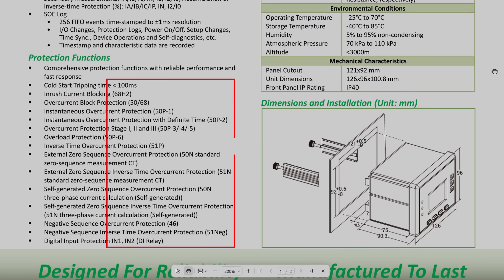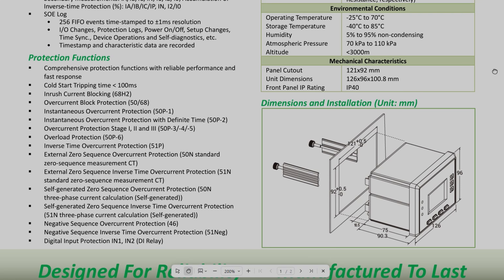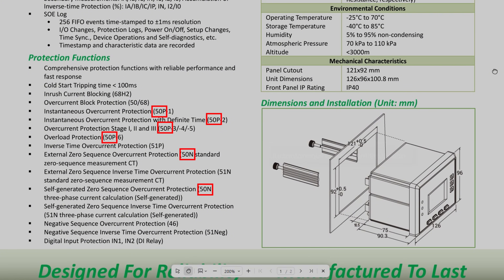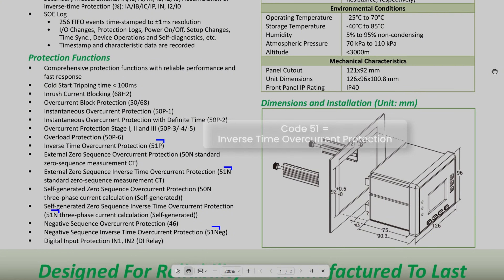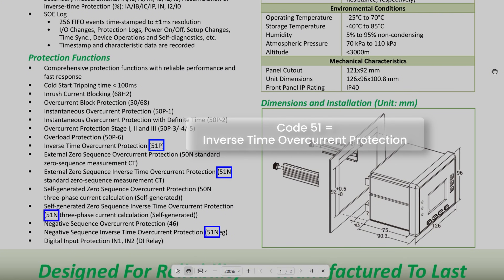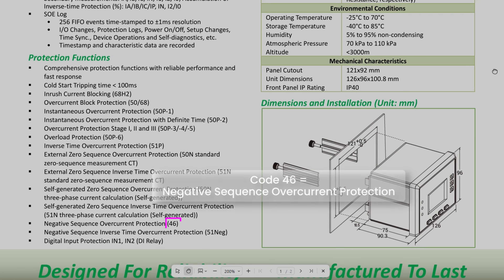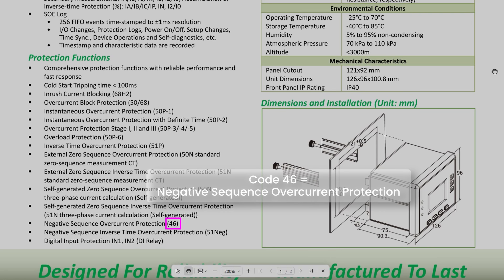You see a bunch of ANSI codes for protection relay here. Basically, the prefix number indicates what kind of protection. 50 means instantaneous overcurrent protection based on phase current. 51 means inverse time overcurrent protection, where trip time decreases as current increases and vice versa. 46 means negative sequence protection against phase imbalance.